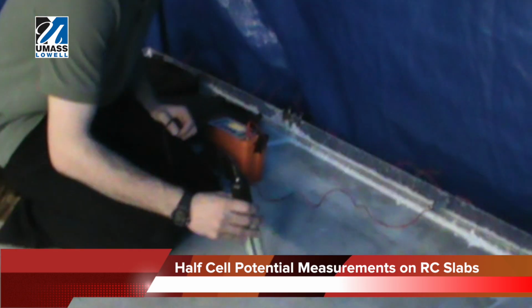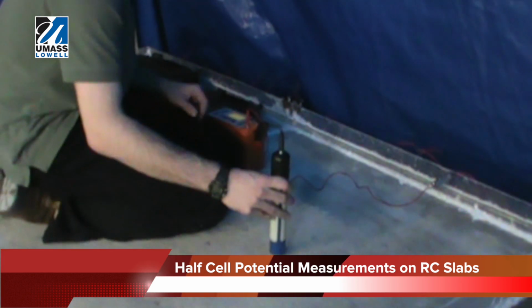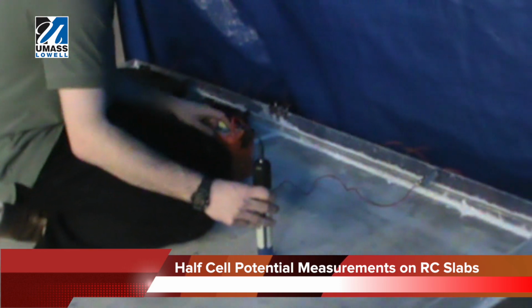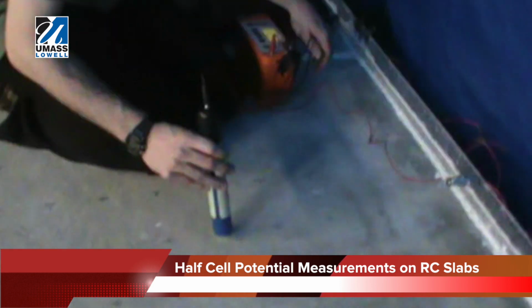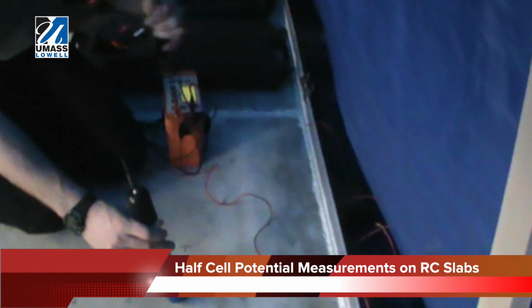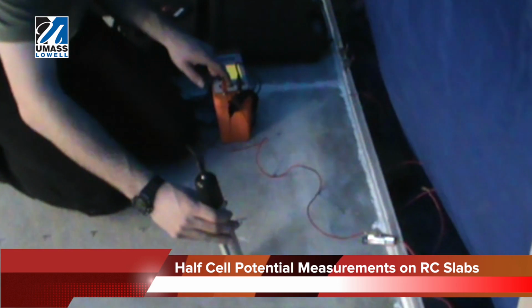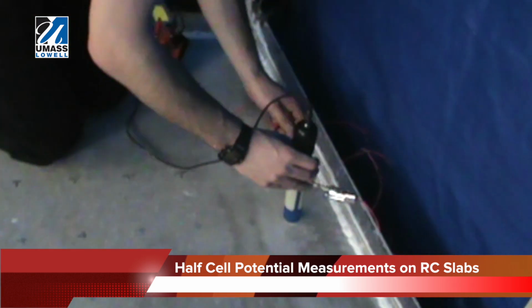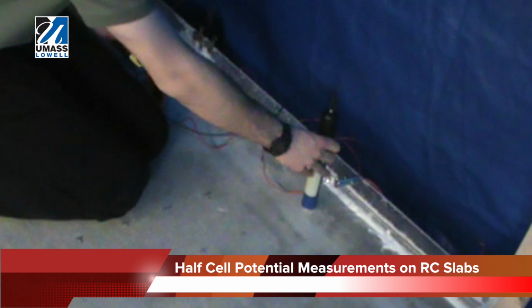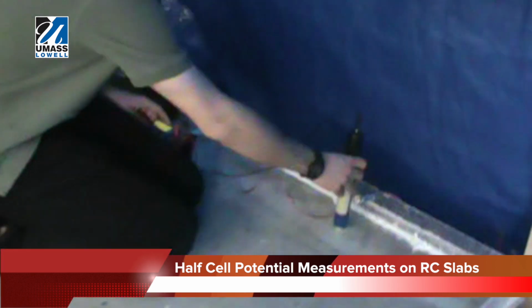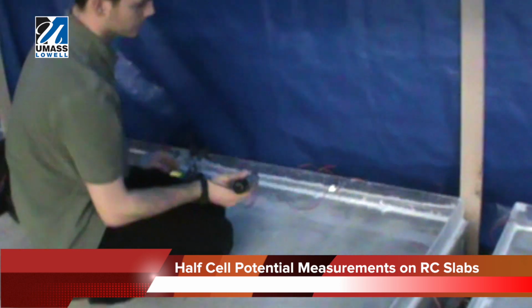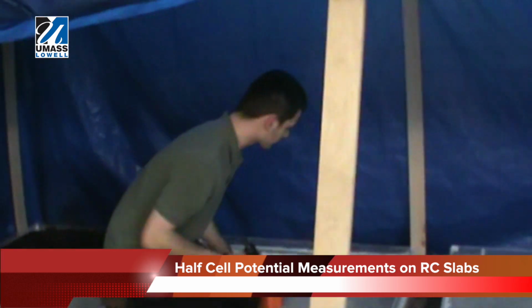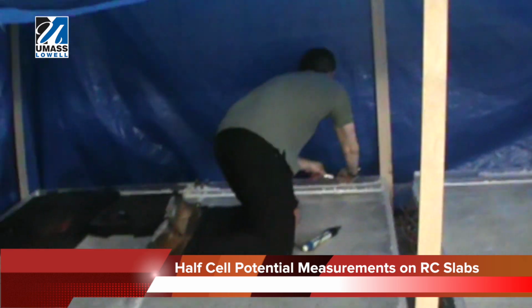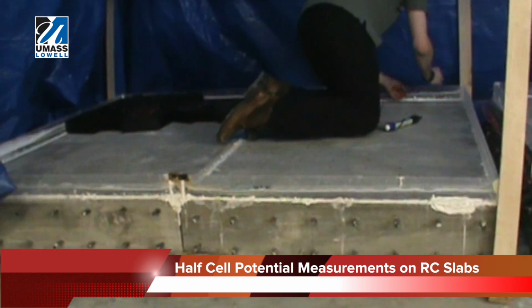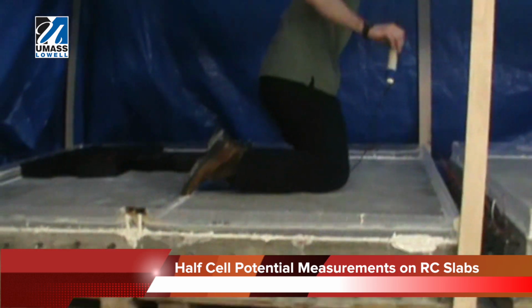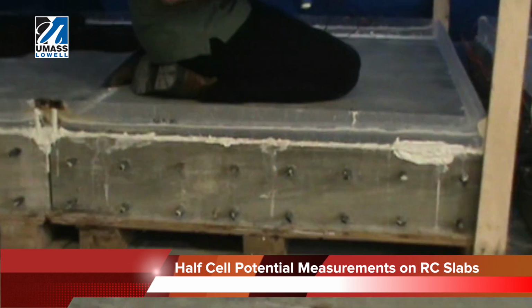The equipment we are using is a 331 MK2SH cover meter and a half-cell reference electrode from Elcometer. The reference electrode that we are seeing in this video is a silver chloride reference electrode. Based on ASTM C876, which is the standard that dictates how we take the half-cell potential measurements, first we are supposed to wet the surface of the slab at least 1 day before taking the measurements of the reinforced concrete slab.